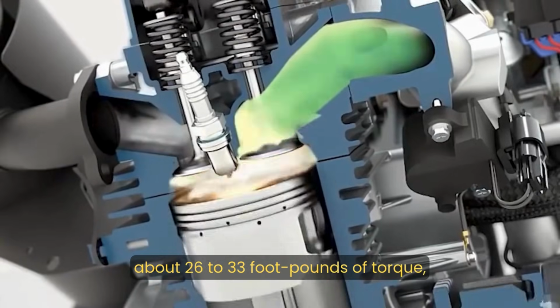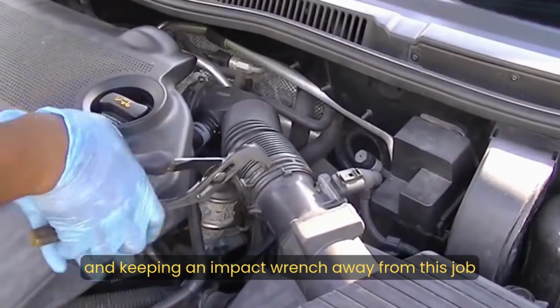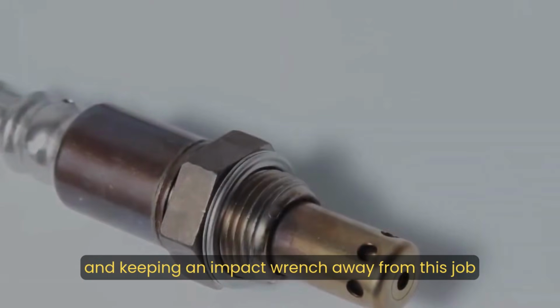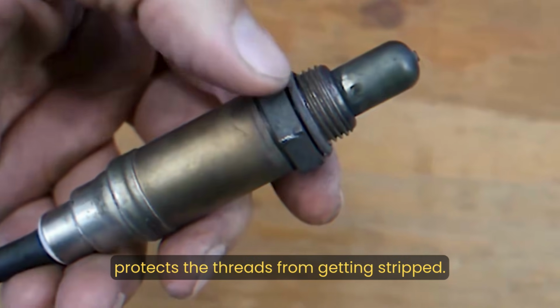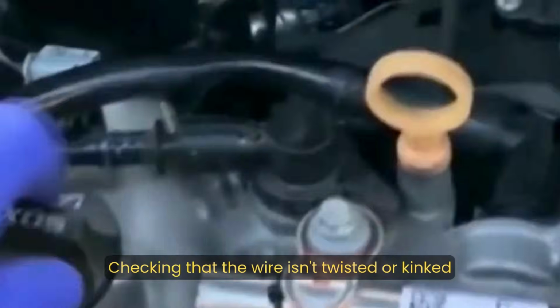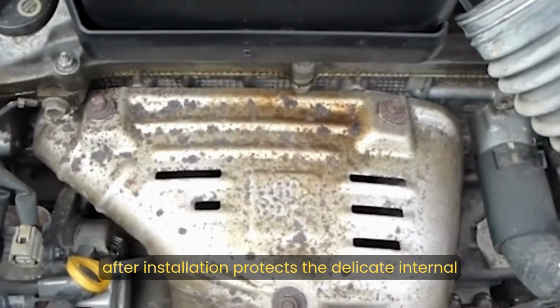Standard M18 sensors call for about 26 to 33 foot-pounds of torque, and keeping an impact wrench away from this job protects the threads from getting stripped. Checking that the wire isn't twisted or kinked after installation protects the delicate internal components from damage.